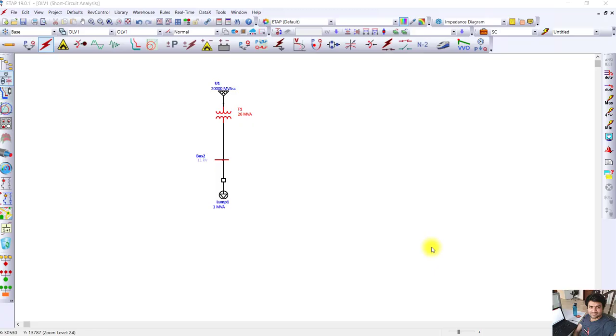Welcome back guys. Now we will see in ETAP we will make a model of a 132 kV network and we will inject fault current - phase to ground fault with solidly connected neutral system and with 5 ohm NGR. We will see how much reduction in fault current occurs if you are using NGR versus not using NGR.